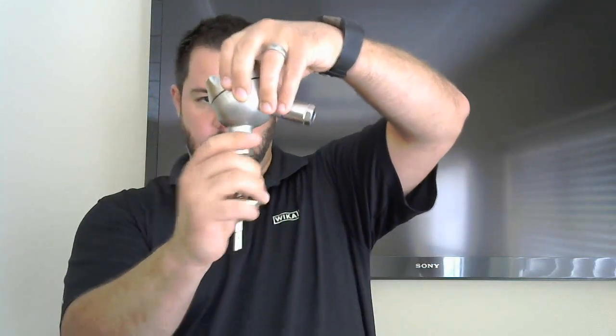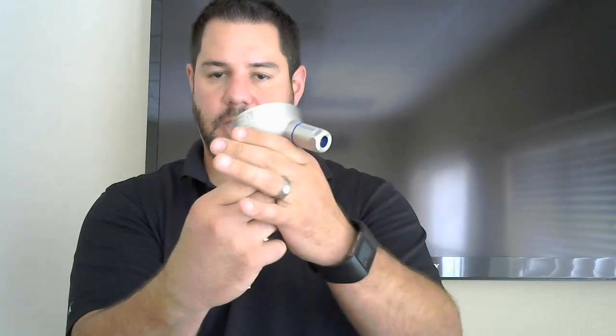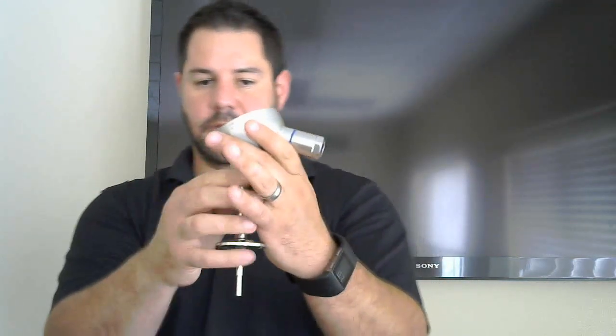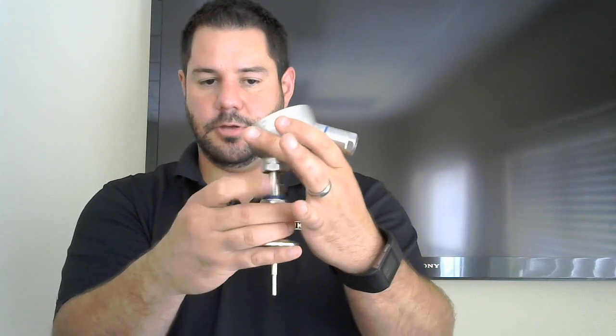A lot of our competitors, when you have to remove them for calibration, the maintenance staff has to go out and actually unwire the RTD every single time, take it out, because they don't have a union nut down here that allows them to just leave it in place. With ours, you can leave it wired up, just undo the union nut, pull the RTD out, put it back in, screw it back in - you never have to unwire it. This makes it much easier on the maintenance staff.